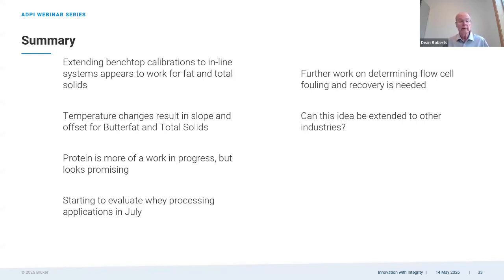We're pretty sure that the temperature changes result in the slope and offset. I think we've proved that, and we're going to work on applying those temperature changes. Protein is still a work in process, and we think it's going to work based on some of the results we got at the milk unloading, but we really need to get a wider range of protein to be sure that that's what's happening. And then we need to extend that work into the whey processing, where we're looking at higher and higher levels of protein. We need to be able to look at those more viscous samples to make sure that the flow cell is not fouling. And if it is fouling, what recovery is needed to keep those results in line with the repeatability and the accuracy expectations. And then we're going to start trying to apply this to other industries.